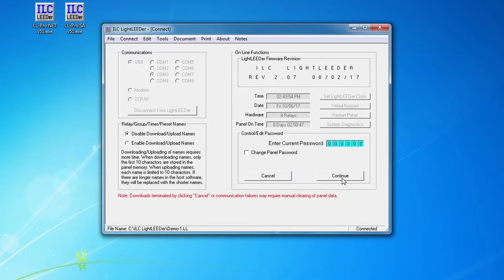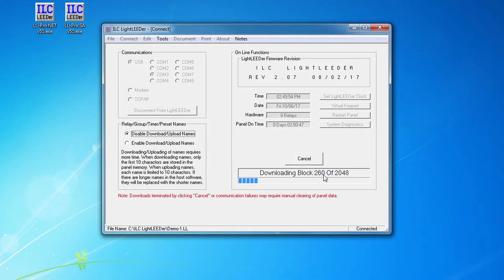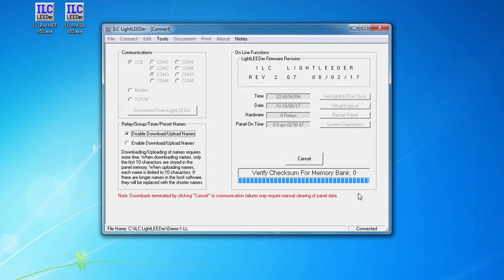It'll ask us do you want to continue - it does give you a chance to say oh no that's not what I wanted to do and you could cancel out of it. You can change the password here if you want to. If we leave it all zeros, it's not going to ask you for a password every time you do this, so we're going to hit continue and it's now going to start downloading those blocks of data to the LightLEEDer panel.